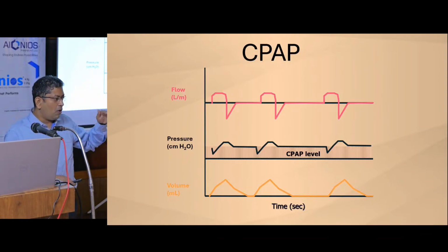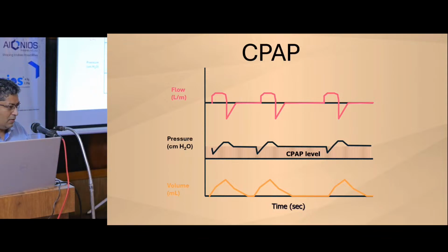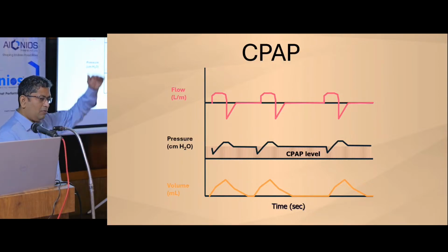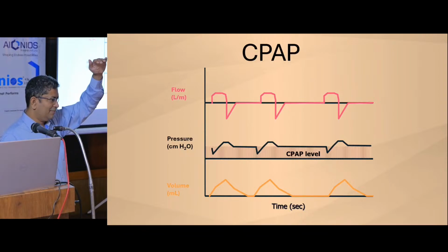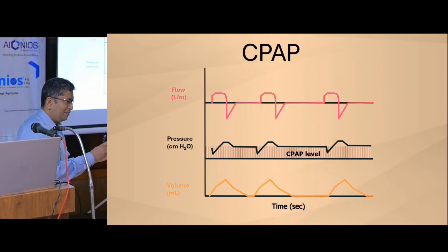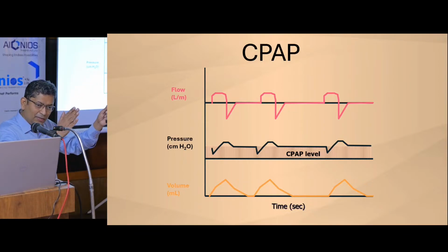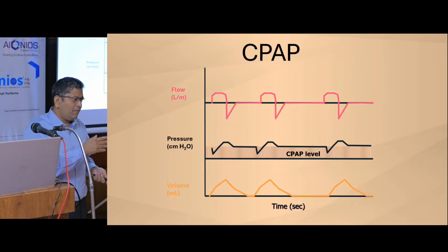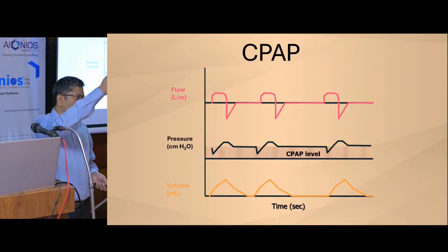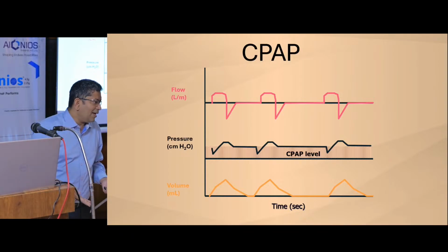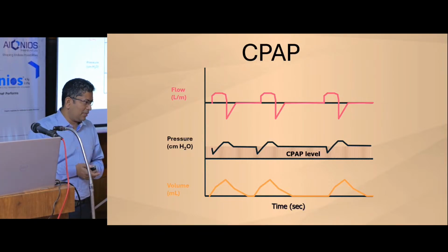But we just do that pressure support. Now, what bi-level ventilators or APRV do is adjust the CPAP. It goes from a CPAP level of 5 to 15, 5, 15. It keeps on changing at a particular rate, and you can adjust the rate and the time it stays on top. So basically, it's something like a pressure control. If you put 20 times a minute, 20 times it goes up, and 1 second it stays up, and then it comes down. So if the patient is paralyzed, it is generally like a pressure control.